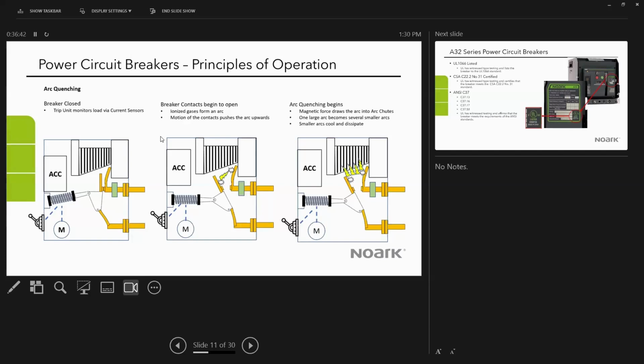And that's what keeps the breaker from basically blowing up as that arc begins to form, because the contacts force the arc upward into the arc chutes, and the arc chutes split it up and dissipate the energy of that arc. So that's kind of the basic principles of operation.